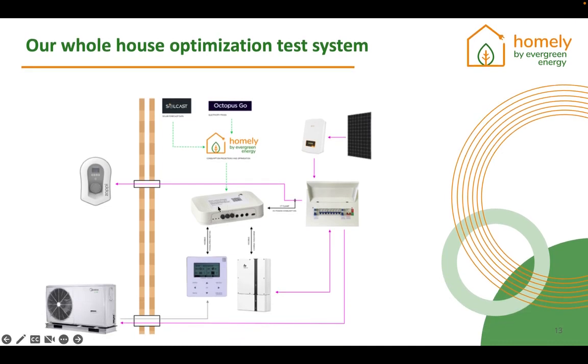So as you can see, Homely here in the center, connected over Modbus connection into the heat pump controller, into the battery, a CT clamp attached to the EV charger so that we make sure that we don't discharge the battery into the EV. We also have Homely Cloud, which gives us solar forecasting data. So we can see a day in advance that there will be PV, for example, available. And even though, as an example, you have very cheap electricity overnight, it might be that it makes more sense to not charge the battery fully because it's a very sunny day and we want to make sure that we have enough room in the battery to soak that PV up.